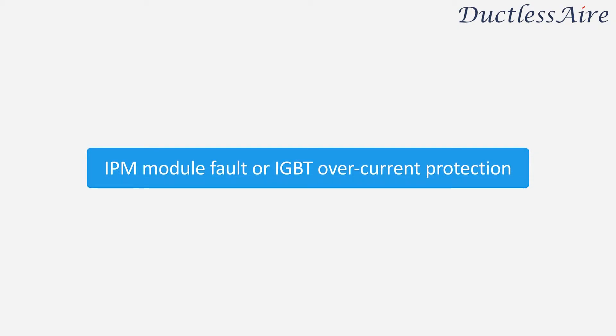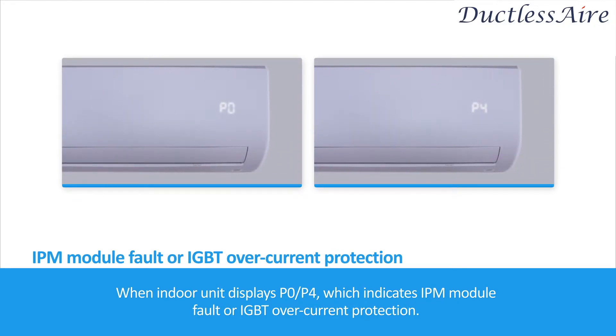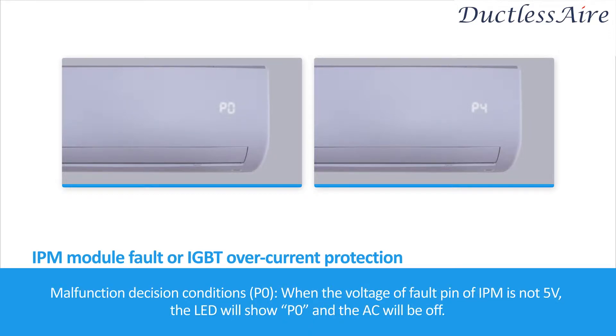IPM Module Fault or IGBT overcurrent protection. When the indoor unit displays P0 or P4, which indicates IPM Module Fault or IGBT overcurrent protection, the malfunction decision condition for P0 is: when the voltage of fault pin of IPM is not 5 volts, the LED will show P0 and the air conditioner will be off.